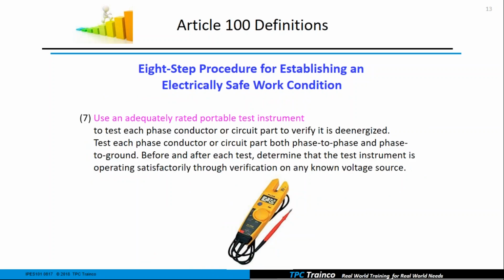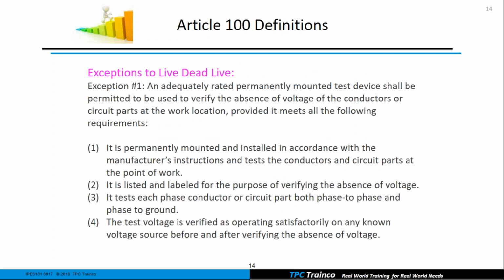And then our live dead live step, so using the right category of meter, we would go ahead and verify that we were de-energized, and phase to phase, phase to ground, so make sure that that says 0, and test our meter before we do that verification step and after. And then lastly, we always had this one, which, well, this one's a little bit different. This one is some exceptions to that live dead live. So this is kind of new.